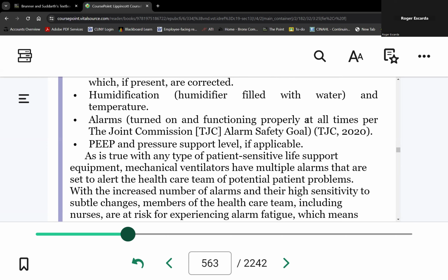Could it be that the airway is inflamed? Yes. Could it be that the patient's airways are narrowed, constricted? Okay, so you have several examples there that will trigger a high pressure alarm. What if the patient develops a pneumothorax? High pressure or low pressure? High pressure, very good.